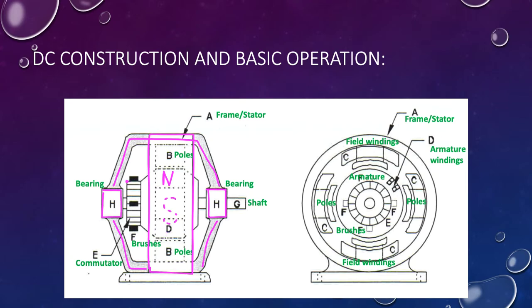My field is only made up of a single field winding with a north and a south, which you'll see in the pictures very shortly. So I have a pole on either side. I have a north on one side. And on the opposite side, which you can't see here, I have a south. Rotating around the inside of the machine, sitting on the shaft, there is the armature. And you can see that here is my armature and my shaft connecting through, sitting inside my bearings. And then on the end of my armature, is my commutator with brushes to take electrical power to my motor.